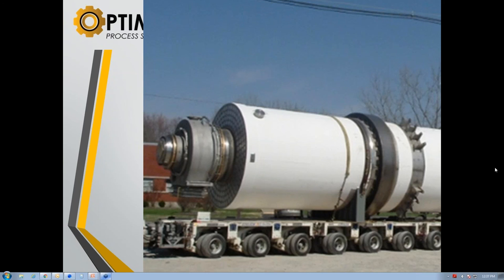Have you seen more rolling than welding on these types of seals? On the tubes? I'm assuming on the tubes. We do probably 60% rolled tubes, 60-40. If the customer wants, our tube sheet on our units is double grooved, so that you bring the tube in and you roll it and flare it.